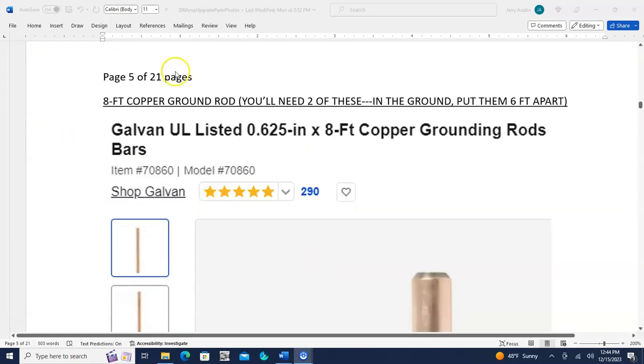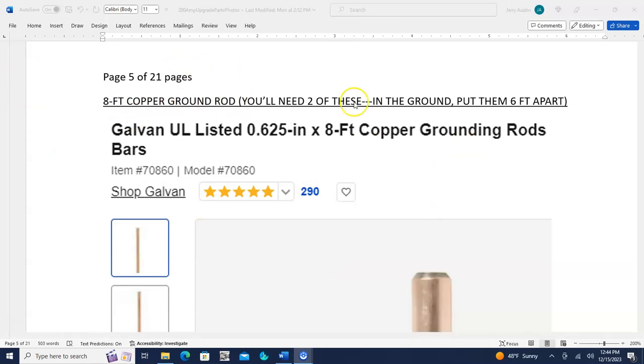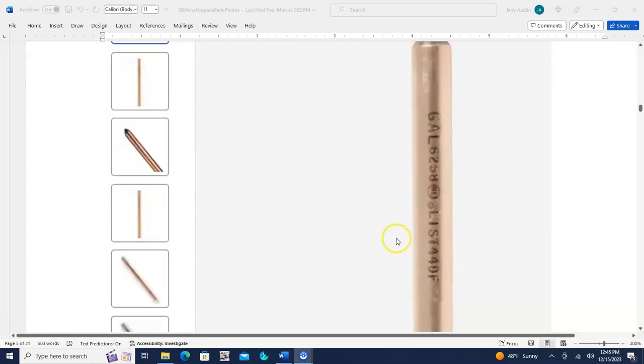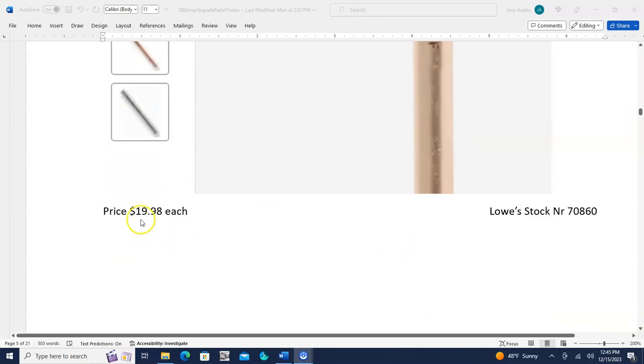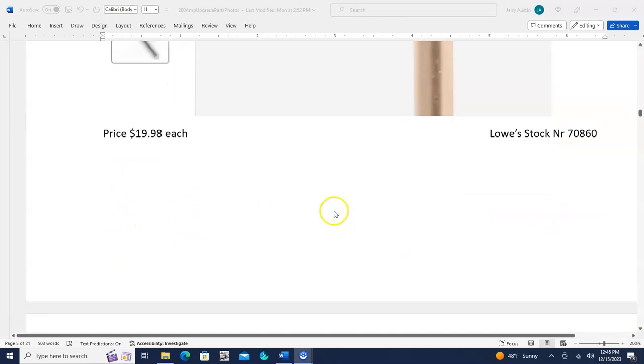These are the grounding rods we bought - 8 foot ground rods. You need 2 of them, and in most jurisdictions they must be put at least 6 foot apart. The solid copper wire runs from one to the other, and it cannot be spliced. They're $19.98 each, and that's a Lowe's stock number.